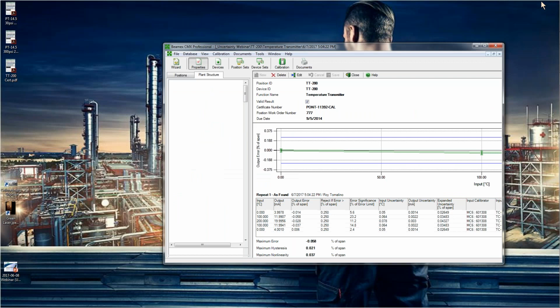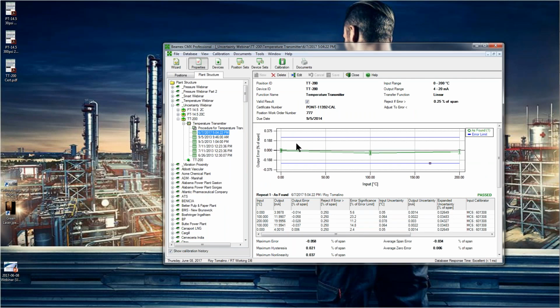But Roy, talk about the numbers in the expanded uncertainty column. So we have our input uncertainty and then the output uncertainty, and then we have the combination, the percent of span. So, Ned, as you were saying, is this our 2-sigma representation? Well, what we do is we take the 0.05 degree C and divide that by span and square it. It's a percentage number. Then we take the milliamps, divide that by 16 because that's the span, and square that number. Then we take the square root of it, and we get the expanded uncertainty column. So what's the biggest number in that column? Because it is hard to see.